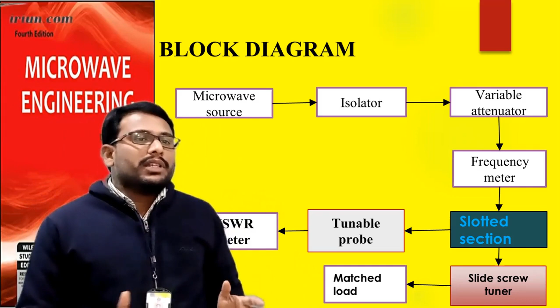Okay, then next, frequency meter. By rotating the frequency meter, we can set a particular frequency to the microwave energy generated by the source. Here we are using the X band. The values start at 8.2 to 12.4 GHz. So this is the exact band in between. So you have to set a particular or exact frequency to the energy.